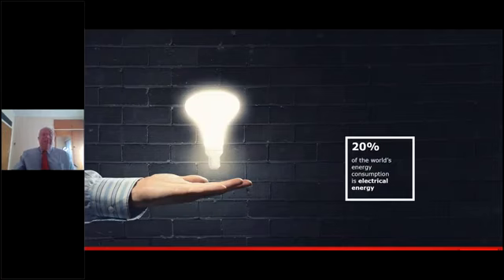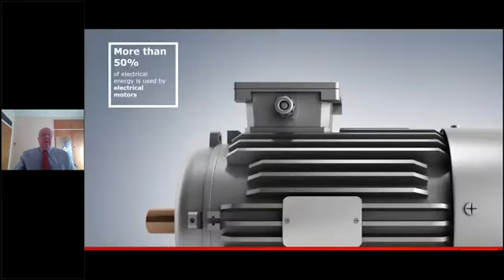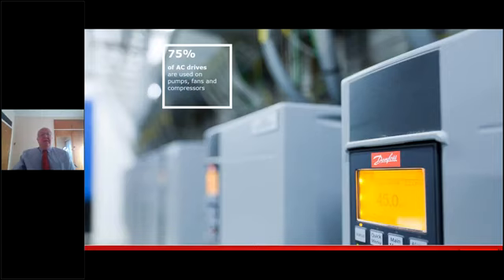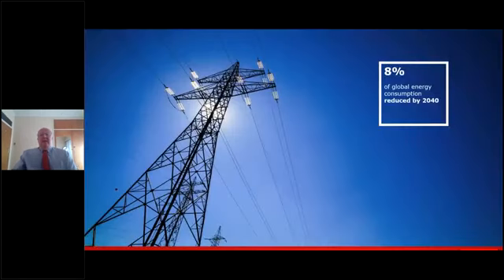So 20% of the world's energy consumption is electrical energy. And very interesting, more than 50% of electrical energy is actually used by electrical motors. That's quite a staggering fact. 75% of AC drives are used on pumps, fans, and compressors, all basically used in the mining industry. And by the year 2040, if we could control the speed of motors or control motors with variable speed drives, there's the potential to reduce the global energy consumption by 8%.